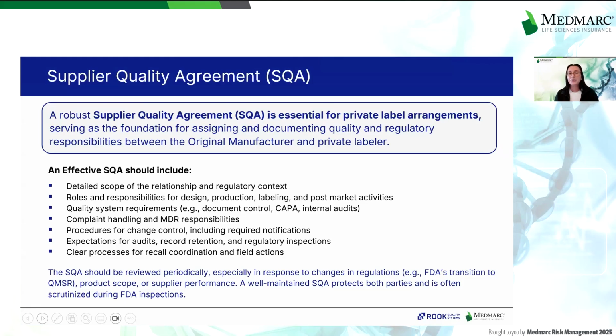An effective supplier quality agreement should include a detailed scope of the relationship and regulatory context; roles and responsibility for design, production, labeling, and post-market activities; quality system requirements such as document control, CAPA, internal audits, complaint handling, and medical device reporting responsibilities; procedures for change control, including required notifications; expectations for audits, record retention, and regulatory inspections; and a clear process for recall coordination and field actions. The SQA should be reviewed periodically, especially in response to changes in regulations.